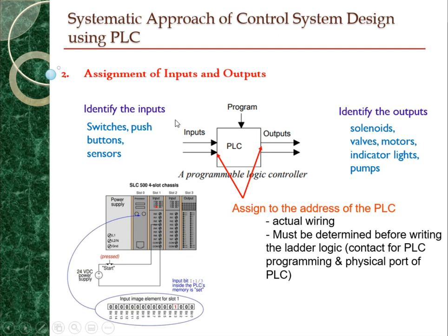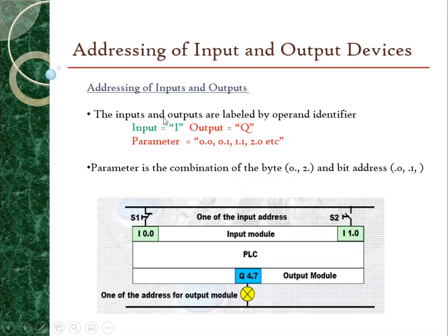Once you have identified all the inputs and outputs, you need to assign them to the addresses of the PLC, because the address determines the actual wiring that you need to connect between your PLC and your external devices. This address must be determined before writing the ladder logic diagram, as it will define the contacts for PLC programming. The PLC has I/O ports assigned to addresses in the PLC memory, so you need to know which port is connected to which external device before you can assign inputs and outputs in your ladder logic diagram.